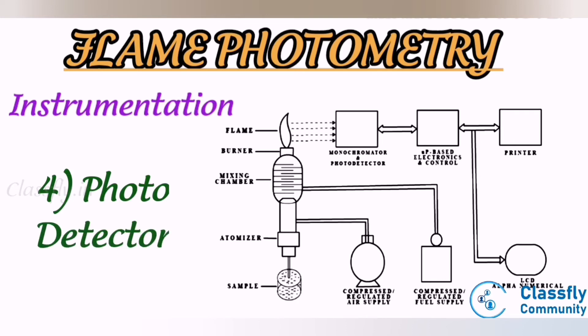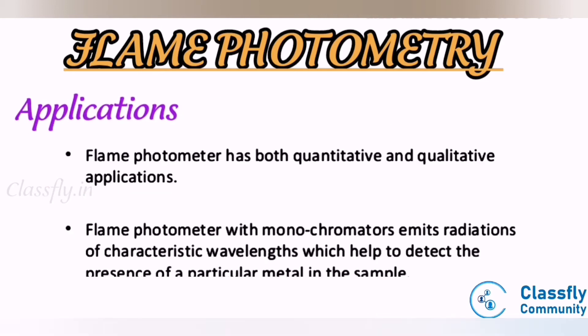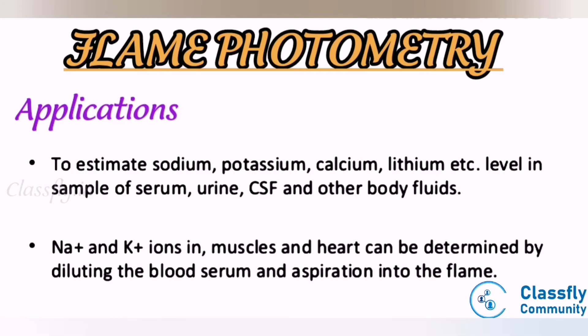The reflection from the mirror passes through the slit and reaches the filters, which isolate the wavelength to be measured from any other extraneous emission, acting as an interference-type colored filter. Fourth, photo detector: it detects the emitted light and measures the intensity of radiation emitted by the flame, converting it into an electrical signal. Applications: flame photometry is used to estimate sodium, potassium, calcium, and lithium levels in samples of serum, urine, CSF, and other body fluids.